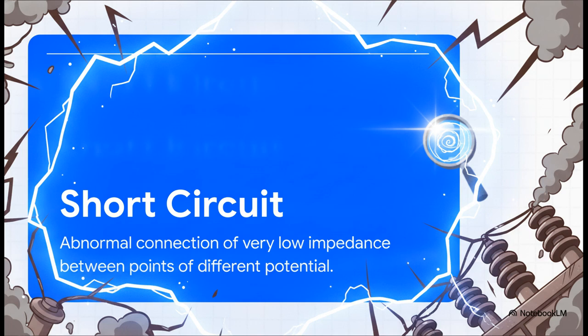On the flip side, we have the short circuit, also called a shunt fault. This is an abnormal connection with very low impedance between 2 points. Basically, think of it as electricity finding a devastatingly easy shortcut. These are by far the most common and most severe disasters engineers face. Because the resistance is so incredibly low, massive currents flow through the lines. If a short circuit is allowed to persist for even a tiny fraction of a second, the resulting heat will completely melt and destroy the equipment.